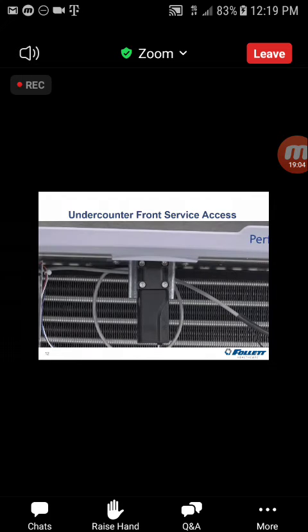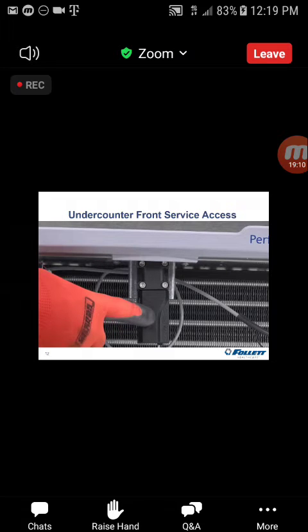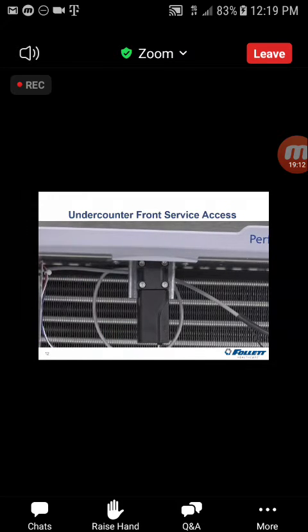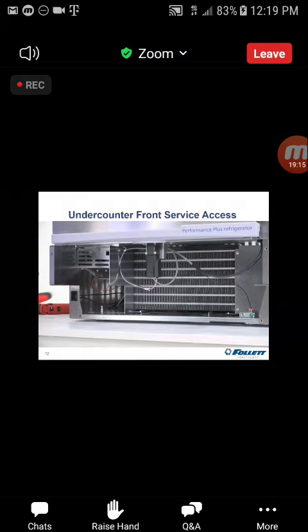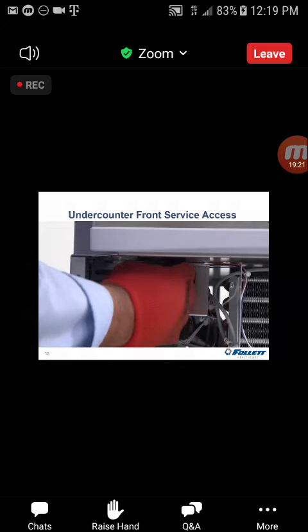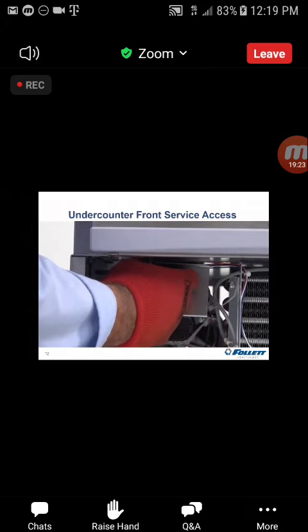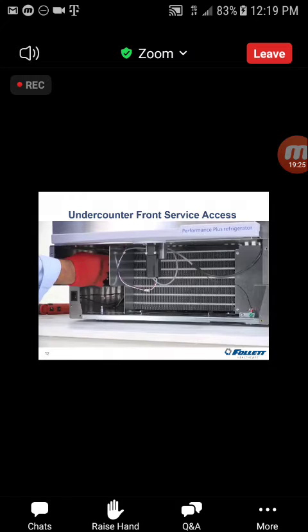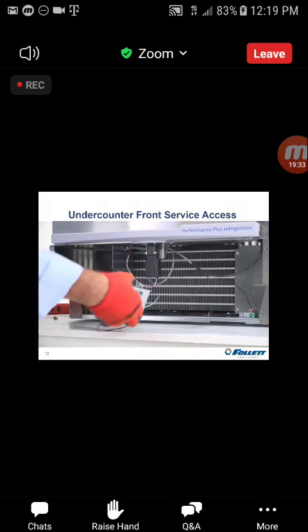In this particular unit, in the center, we can see the lock mechanism for the keypad lock. This is found only when the Follett keypad option is installed at the factory. The electrical box is accessed on the left-hand side of the unit. To remove the electrical box, loosen and remove the vertical knurled screw. Then the front of the electrical box will drop down slightly and it can be pulled forward and laid in front of the refrigerator.